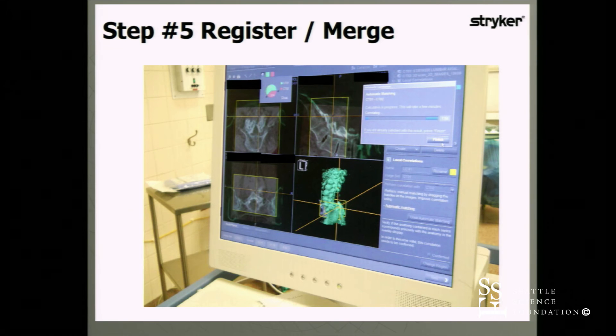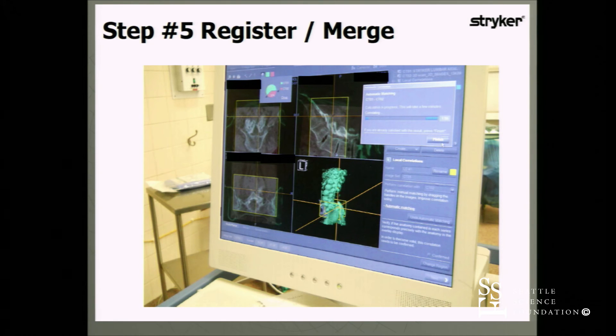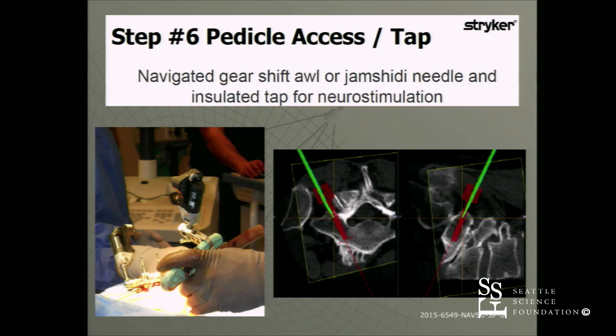This shows the registration process — we take the intraoperative spin and fuse it to the preoperative volumetric CT scan. The computer allows you to take the green image, which is the 3D spin from the OR, line it up to your volumetric CT as best possible, and then hit automatic correlation. The average time for the computer to complete this is about 19 seconds. Once done, the red image represents the planned screw trajectory, and the green image is the navigated instrument following that same pre-planned trajectory.